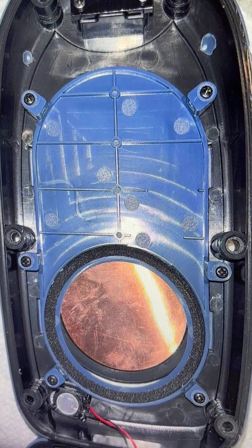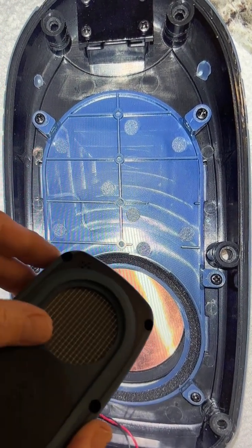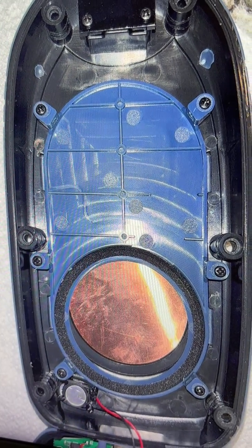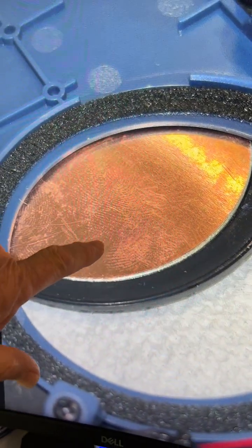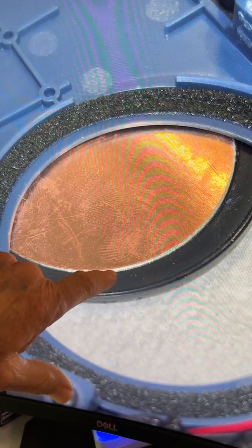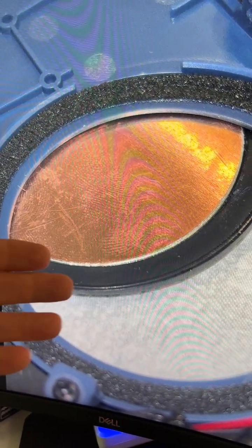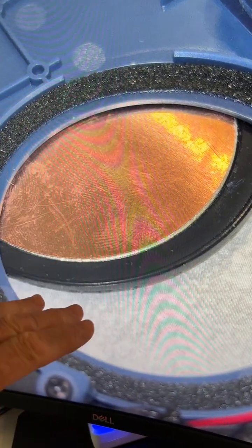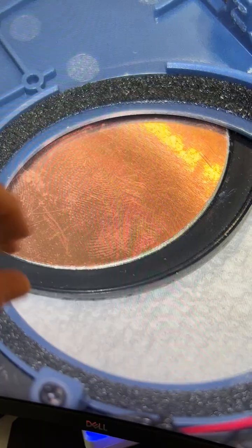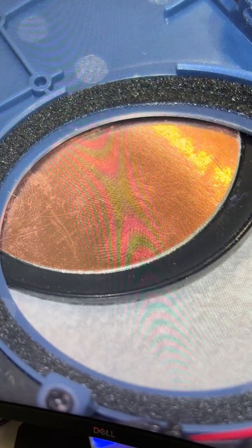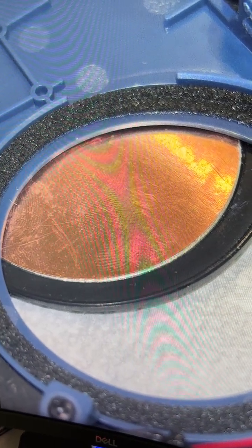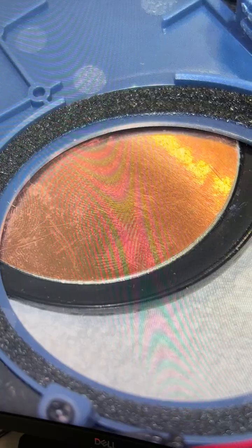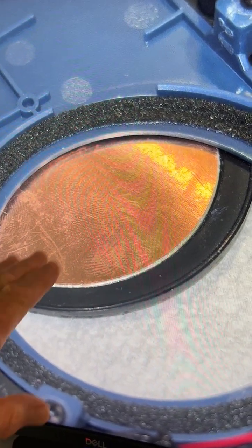This is the energy compensating shield, which I discussed earlier. That's this portion here that slides open and close. And it's composed of, visually I can see copper. The other components I can't really see. What this does is it reduces the braking radiation when you're measuring items where you want to block the beta and the alpha, and it keeps the beta, through bremsstrahlung, from creating a photon and giving you an erroneous reading. So normally it's composed of different materials like plastic, paper, aluminum, and in this case copper as well, to slow the particle down. You can search the internet about braking radiation and learn more about that. But basically it's nice that it has that.